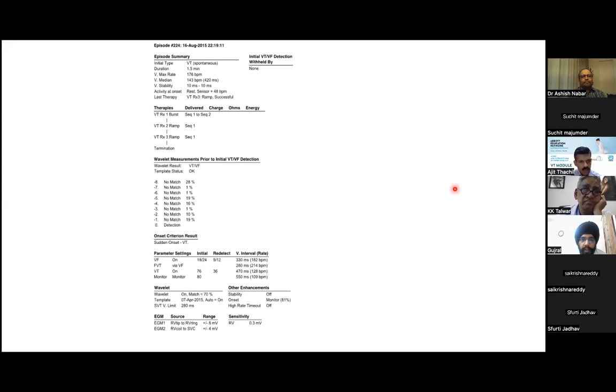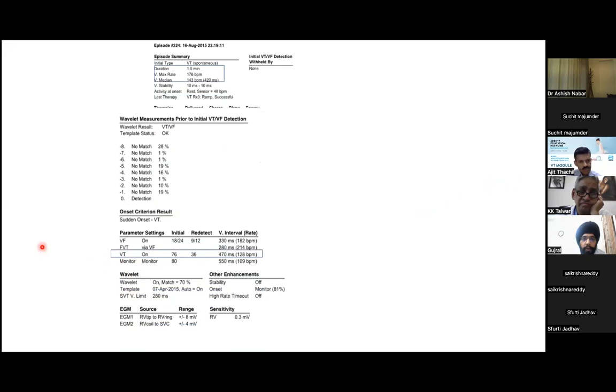So the sequential way to analyze it would be, first, see the parameters. So one sees up, this is the VT zone. You compare the rate and duration of the VT that happened, that is at the top column. The median rate is 420 milliseconds, which is less than the 470 that has been set. So the rate is satisfied. Then you see the duration. The duration here is 76 beats. It will come out to be around 40 seconds. So the duration is 1.5 minutes. So rate and duration are satisfied.